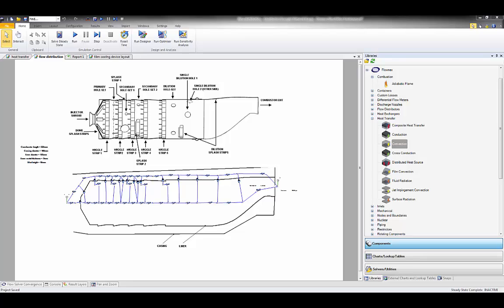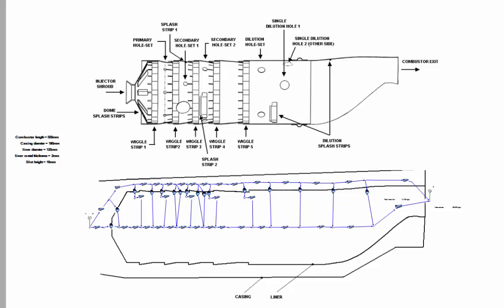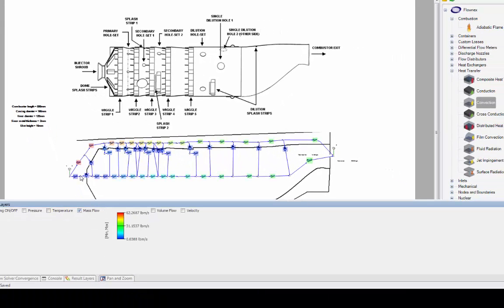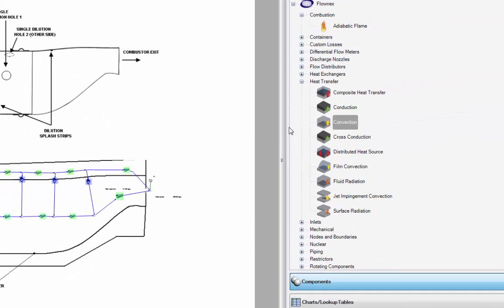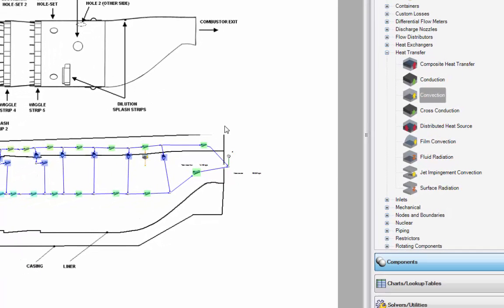What you can see is the flow distribution network laid out on the Flownex drawing canvas. Inputs to the flow components are pretty standard: cross-sectional flow areas, flow path length, various admission hole diameters, and discharge coefficients. This network gives a look at the mass flow and pressure drop through various sections of the liner. Once happy with those results, you can select components from the heat transfer library that incorporate all of the correlations discussed, and integrate the heat transfer components with the cold flow model.